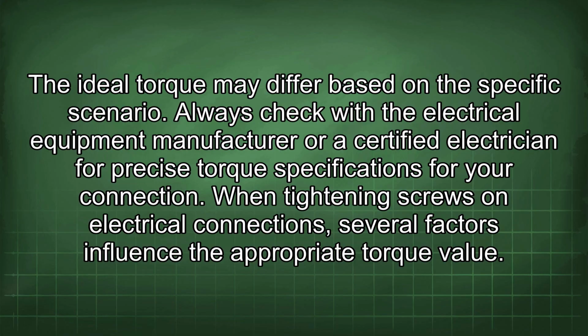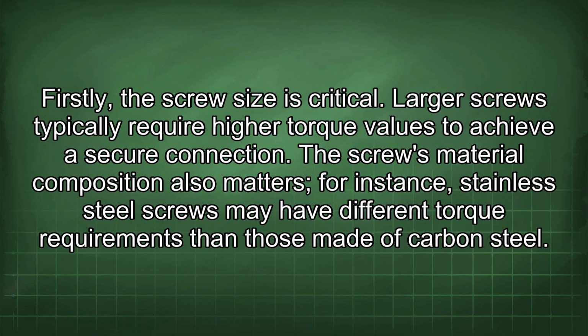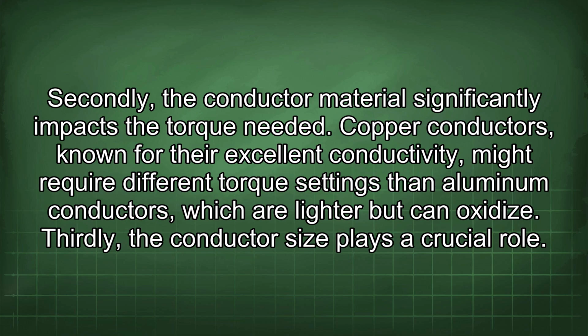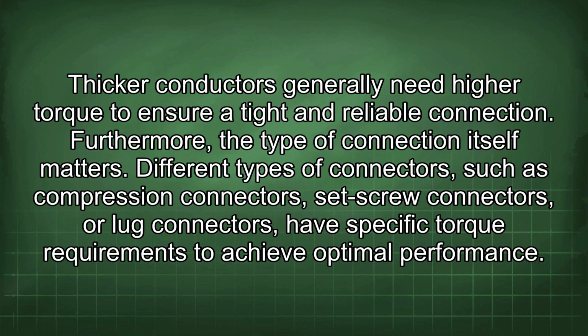When tightening screws on electrical connections, several factors influence the appropriate torque value. Firstly, the screw size is critical. Larger screws typically require higher torque values to achieve a secure connection. The screw's material composition also matters. For instance, stainless steel screws may have different torque requirements than those made of carbon steel. Secondly, the conductor material significantly impacts the torque needed. Copper conductors, known for their excellent conductivity, might require different torque settings than aluminum conductors, which are lighter but can oxidize. Thirdly, the conductor size plays a crucial role. Thicker conductors generally need higher torque to ensure a tight and reliable connection.